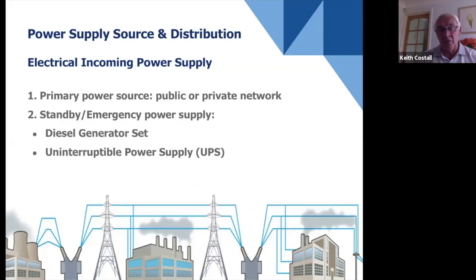Now, it is constant voltage. So in our substation or vault, we take the constant voltage and convert it to constant current output at the CCR. But if we lose that constant voltage input, we need standby equipment, because depending on the operation of the aerodrome there are category 1 instrument runway operations, category 2, and category 3. For category 1, in the event of power failure, we have to get our lights back on in 15 seconds. For category 2 and 3 operations, we have 1 second.